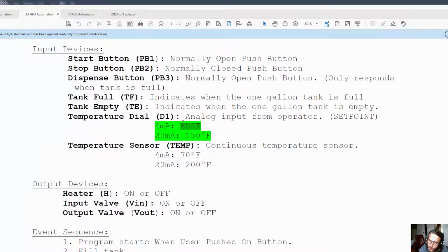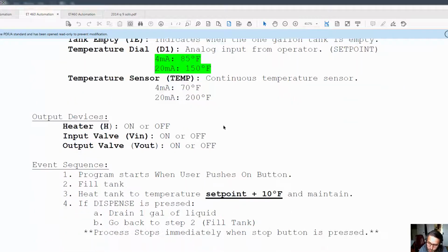But what do you do to make these bits in the dial agree with the temperature sensor bits? This is extremely common in instrumentation. When you're calibrating an industrial sensor, they always work on a range like we've been talking about all semester. You have to set the span and you have to set the 0. So in this variation, we must do both.